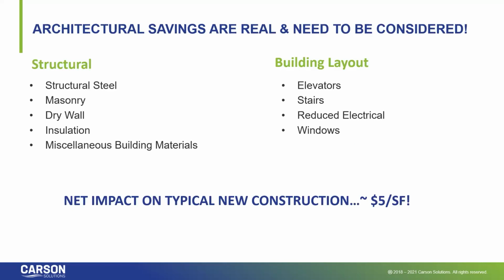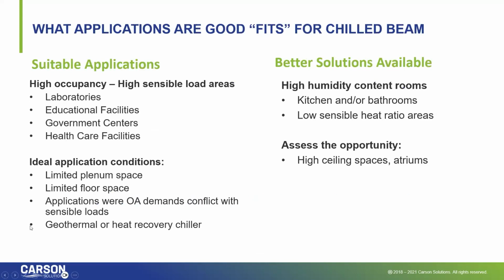So when you start talking about that reduction, we're talking structural steel, masonry, drywall, all sorts of building materials, and the net impact on a typical new construction can work its way on up to about $5 a square foot of savings. What type of applications are suitable for chilled beams? Certainly laboratories, government, educational, healthcare, limited plenum spaces or floor spaces, geothermal, heat recovery chiller applications.